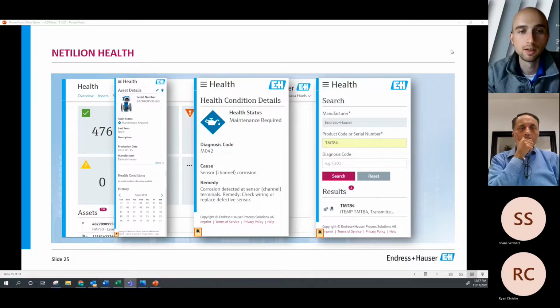These further screens dive in deeper. So if something is in fault or error, it will give you a remedy-based description of what to check. That image in the middle shows at the bottom the remedy - corrosion detected on the sensor was the example for a mag meter. So instead of just giving you an error code and making you dig through a manual to find what that means, it gives you actual text information to troubleshoot further.